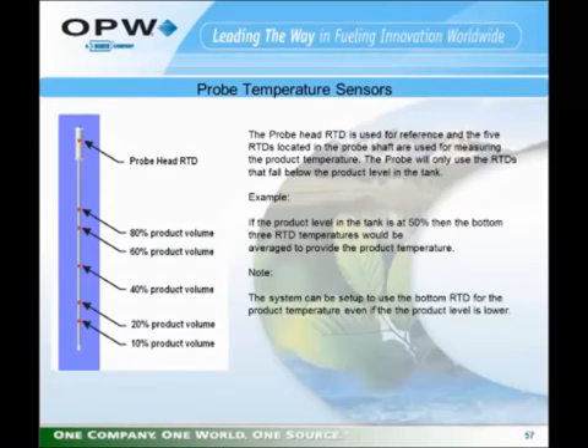The probe head RTD is used for a reference, and the 5 RTDs in the probe shaft are used for measuring product temperature. When computing net volume measurements, only those RTDs that are immersed in product are used in that calculation. Any above the product are not used. If the product level's at 50%, then the bottom 3 RTDs are used. The system can be set up to use the bottom RTD for the product temperature even if the product is lower than the bottom RTD.